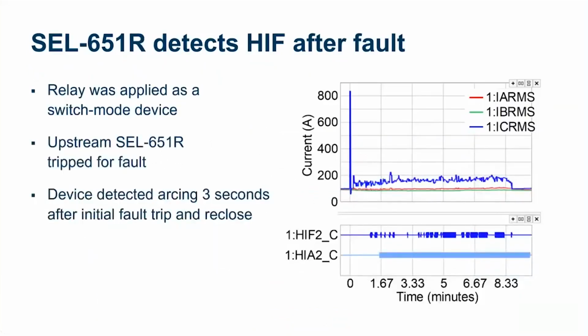Next, I'm going to talk about an actual field event. This is a very interesting event. In this specific event, there are two 651Rs involved. One is the upstream 651R and one is a downstream 651R. The downstream relay is used as a switch mode device. So you can see that the upstream device actually saw a fault current of about 800 amps, and it tripped the 651R and went into that reclosing cycle. But as soon as the relay tripped, the downstream relay started seeing this arc. So you can see that once the upstream relay cleared the fault, my fault current went from 800 amps to a very low value. You can see that there is nothing on A and B phases, a very, very low amount of current or very low amount of arcing.